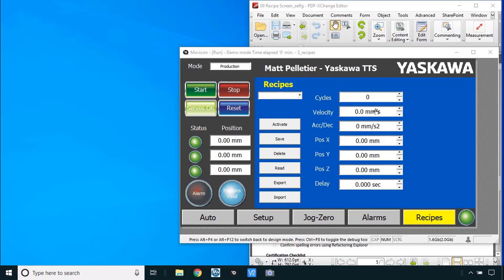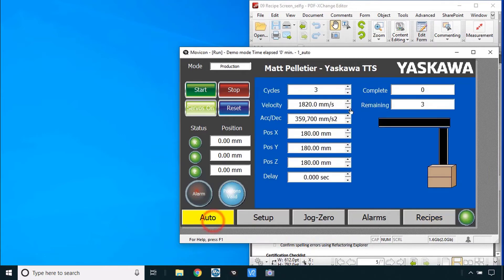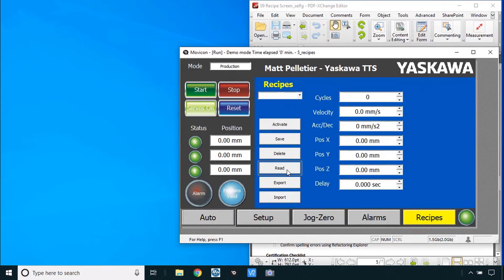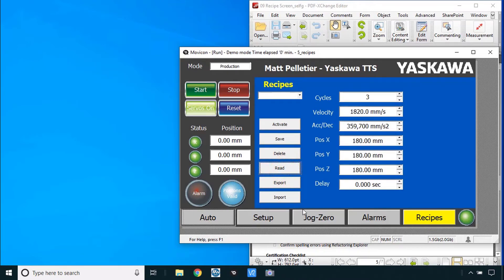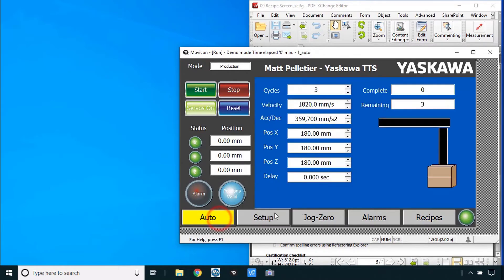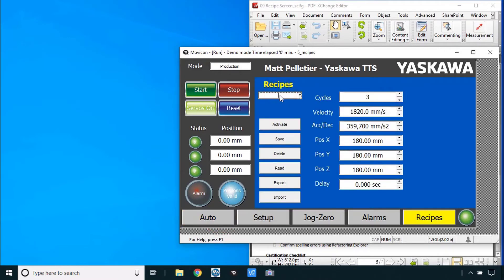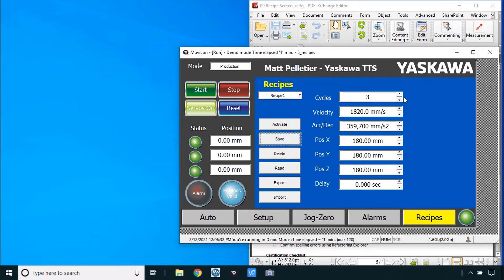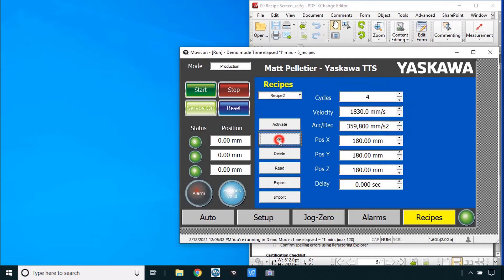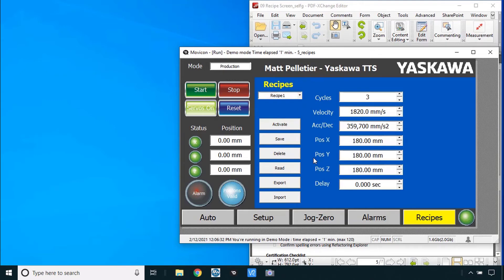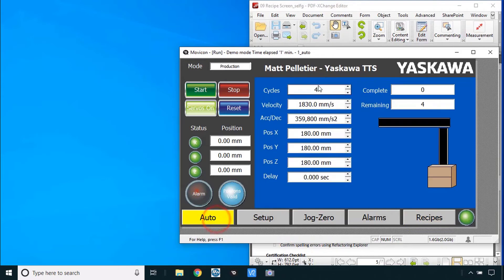And now you see I have all zeros here in the temp variables. But that's not what we have in the auto screen. So let's just do a little test here if I can read it in. Did they all read in correctly? Seems like it's the same data. Let's see if I can save one of these. Recipe one. Save. And I'll change a little bit here and save recipe number two. And see if I can go back to recipe one. Yep, that worked. I'll choose recipe two and activate it. Now the auto screen has the data from recipe number two.